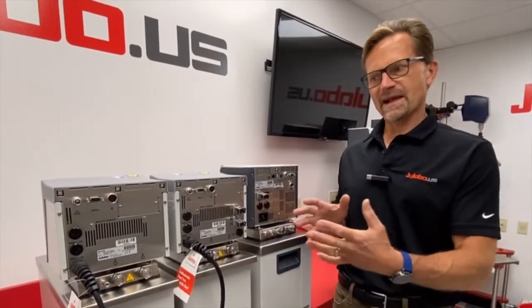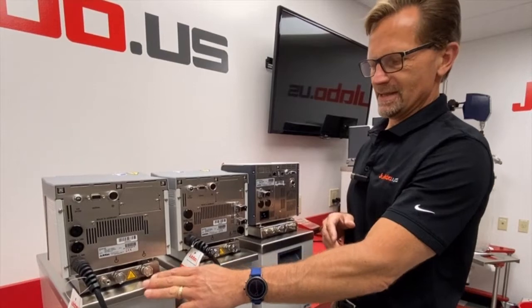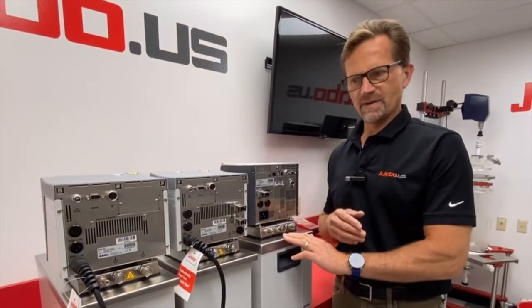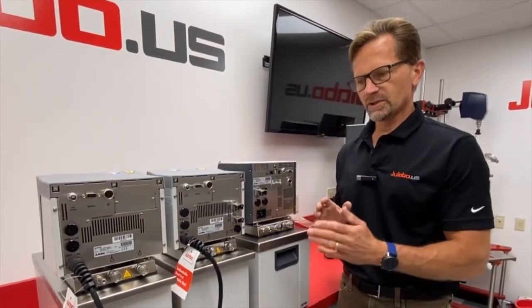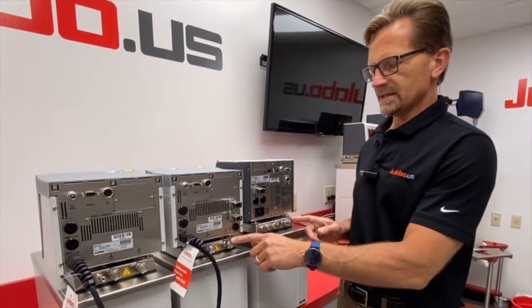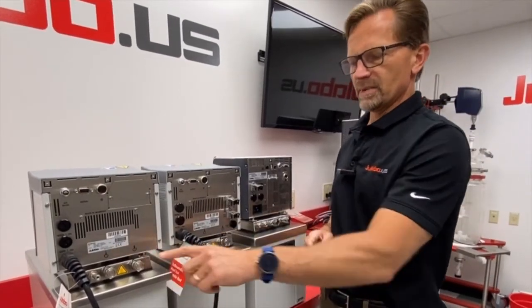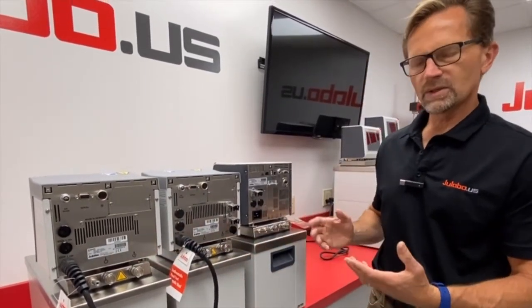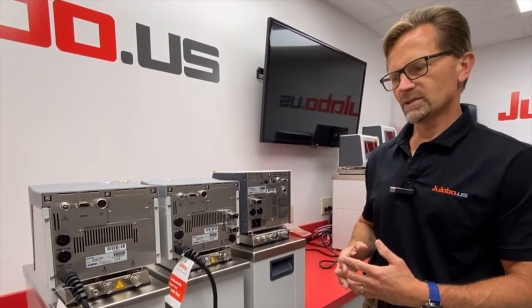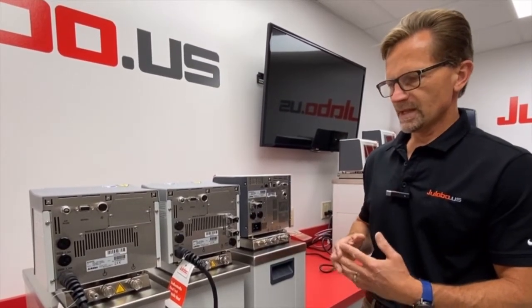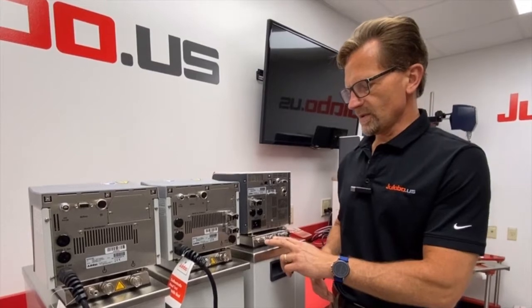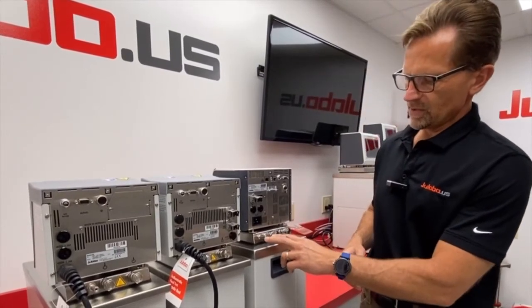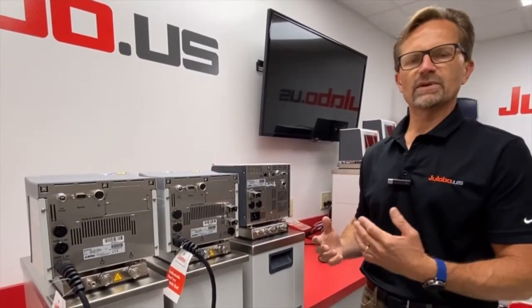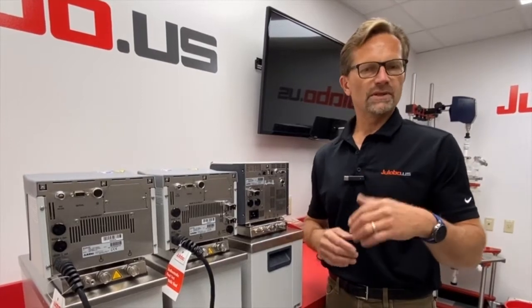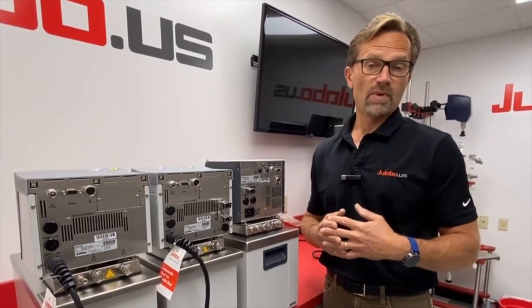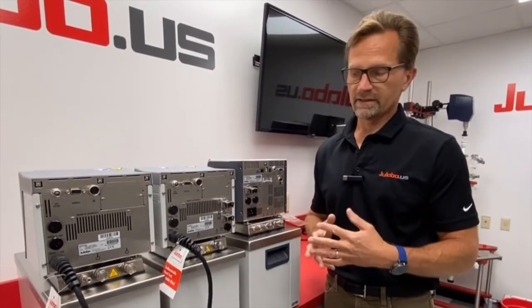All right, so let's look at the back of the units. We have the SE, the SL, and the MAGIO MX. All units are similar in that they have M16 male threaded pump connection fittings. All units come with a pair of 8 and 12 millimeter hose barbs. In addition, they have an integrated cooling coil, which you can see these ports here. So if you want to do active cooling from a high temperature, you can connect this to tap water and then it'll cool it down actively.